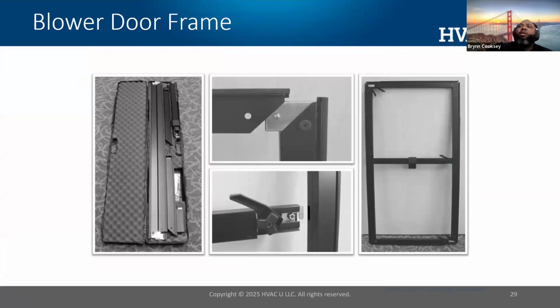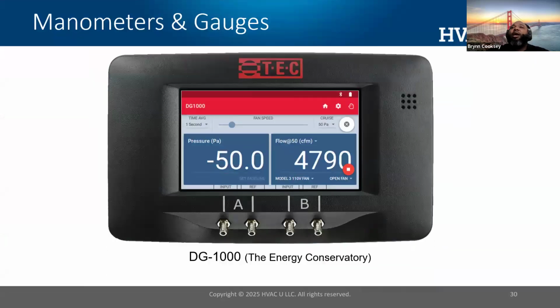When you're looking at the blower door, quite simply, you're putting together a frame, you're going to wrap a shroud around it, and you're going to install it and the fan inside the blower door, and you're going to operate some type of pressure gauge. This is the test pressure that we're looking at, our negative 50 pascals. And on the right here, we see that we have a flow at 50. That flow at 50 represents how many basketballs of air I have going into and out of the house every minute.